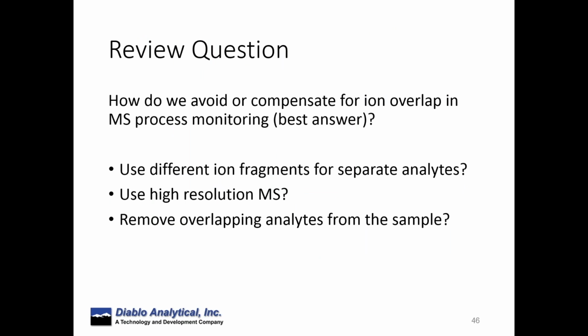Okay, and so now, how do we avoid or compensate for ion overlap? Well, we could use different ion fragments for separate analytes. And yes, if that's possible, that is the first thing to do. Use a high resolution mass spec. That would be a possible way to go, but it would be more expensive and is much more limited in availability. So that's a way of saying this is not a high resolution mass spectrometer. This is a single unit mass resolution device.